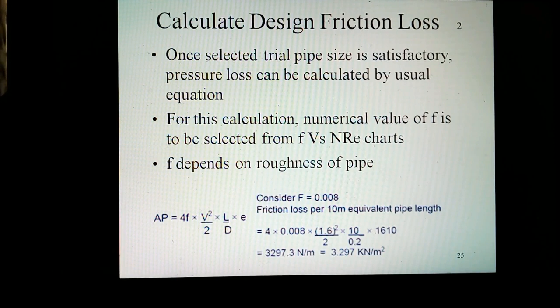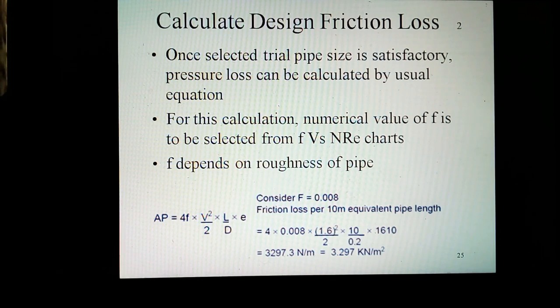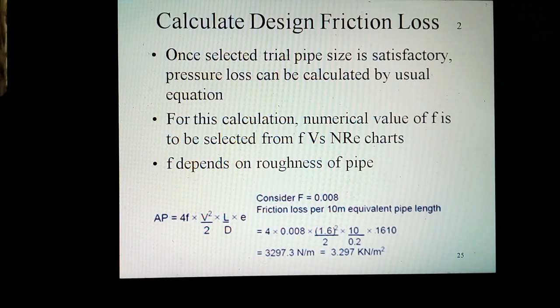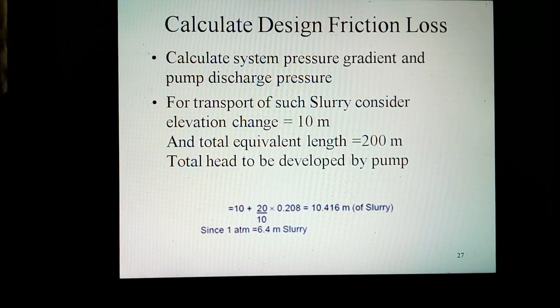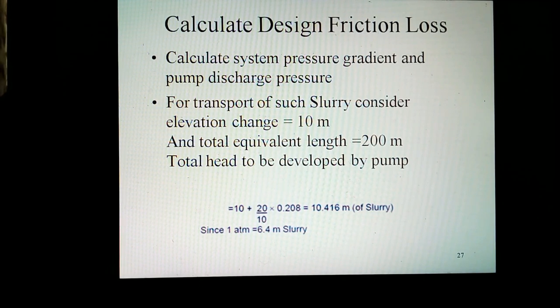Once the selected trial pipe size is satisfactory, the pressure loss can be calculated by the usual equation. For this calculation, the numerical value of f is to be selected from f versus Reynolds number charts. Since f depends on roughness of pipe, a roughness union factor of 100 is considered. It is common practice to express friction loss per unit length. For this purpose, equivalent lengths of fittings, etc., have to be taken into account. Calculate system pressure gradient and pump discharge pressure for transport of such a slurry, considering an elevation change of 10 meters and total equivalent length of 200 meters. Calculate total head to be developed by the pump.